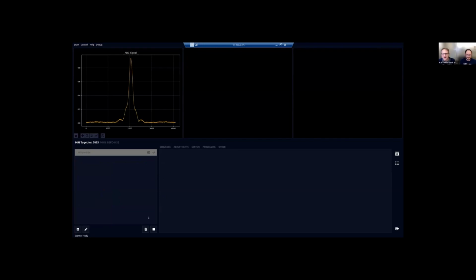By pressing this plus button, you can insert a sequence into the scan queue, and we already have a bunch of sequences, some of which are test sequences, but also a bunch of imaging sequences. Just for demonstration purposes, I will insert, as a start, an acquisition of a spin echo. We have this demo sequence called RF spin echo. If you click on this, you can change the parameters and then start the scan. I'm going to run the scan now. Of course, it's only acquiring a spin echo without any gradients. And then you can see the result, the acquired signal plotted here in the viewer.